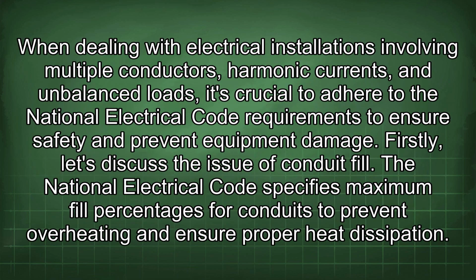When dealing with electrical installations involving multiple conductors, harmonic currents, and unbalanced loads, it's crucial to adhere to the National Electrical Code requirements to ensure safety and prevent equipment damage. Firstly, let's discuss the issue of conduit fill. The National Electrical Code specifies maximum fill percentages for conduits to prevent overheating and ensure proper heat dissipation.